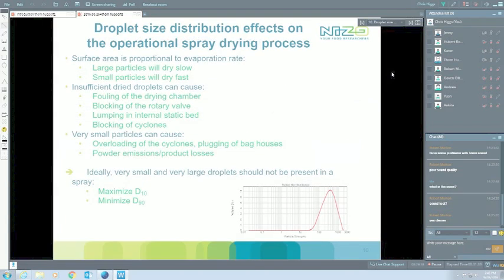Because as we said, droplet size distribution during atomization in the dryer is really one of the key operational aspects. When we look at the droplets themselves and the drying, surface area is really proportional to evaporation rate, meaning how quickly the droplets will dry. Large particles are going to dry slowly. Small particles are going to dry fast, and sometimes extremely fast. On the one hand, of course, we want to avoid poorly dried droplets. They're going to foul the drying chamber, they're going to block rotary valves. They can give us a lot of lumping in the internal bed. We can also get a lot of blocking of cyclones if we don't dry well enough.